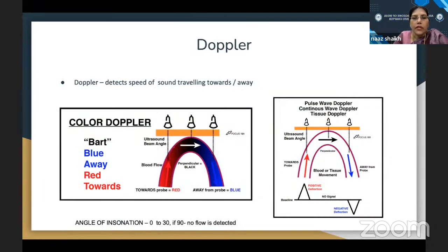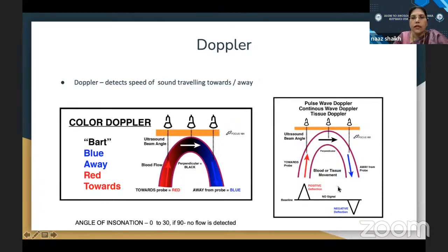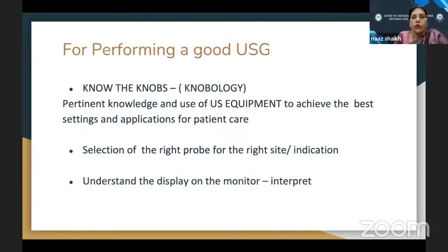In color Doppler, blood vessels moving away from and towards the transducer have different frequencies captured as color. Blue indicates flow away and red indicates flow towards the transducer — it does not tell you whether it is a vein or artery, just the direction of flow. When put on X and Y axes, positive deflection is taken as towards and negative deflection as away from the transducer. To perform good ultrasound, you need knowledge of knobology — the pertinent knowledge and use of ultrasound equipment to achieve the best settings. Selecting the right probe for the right site and indication is very important.